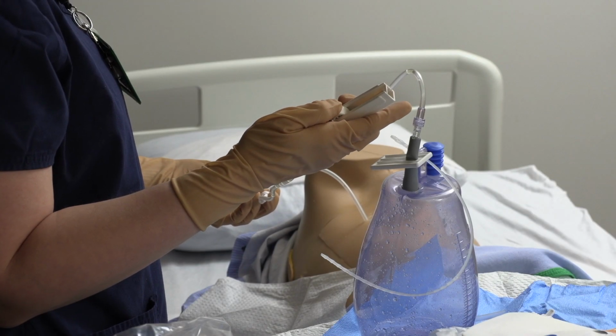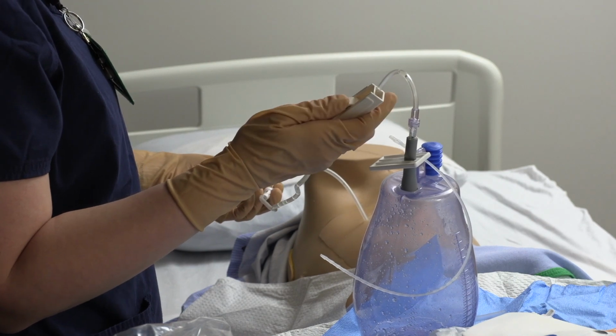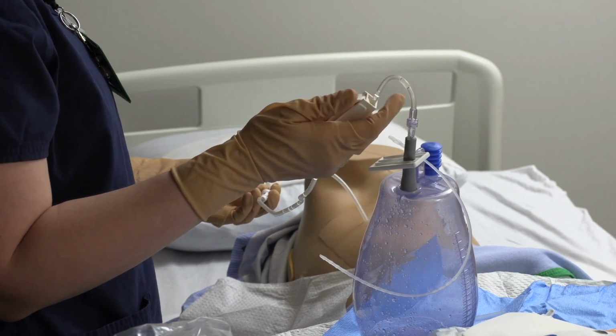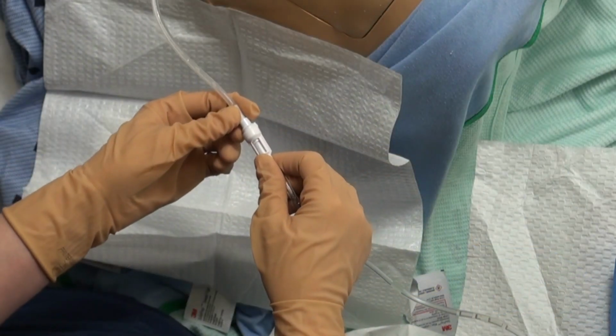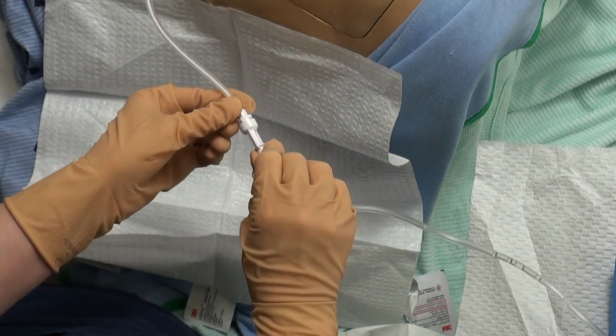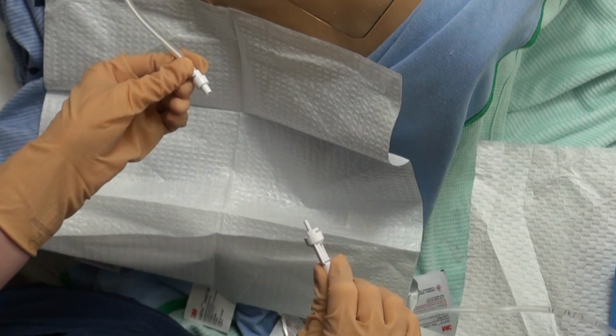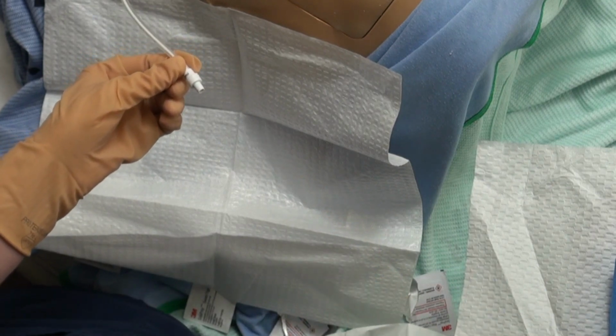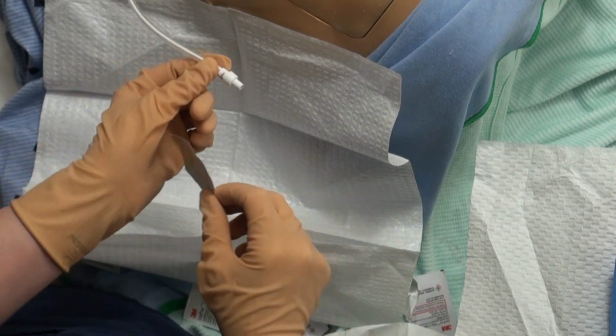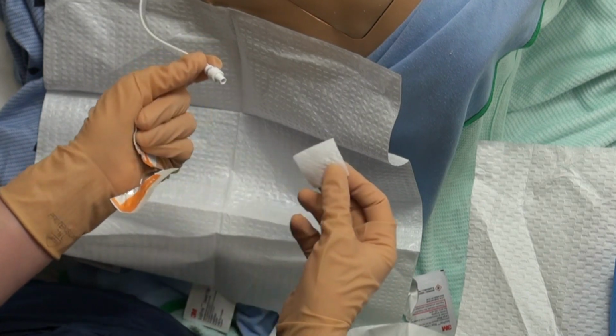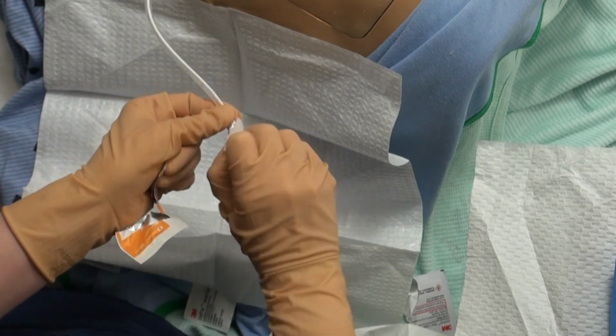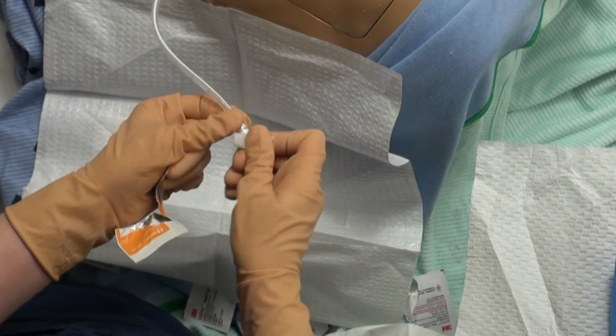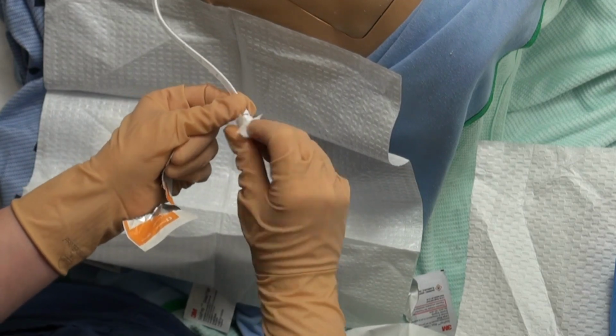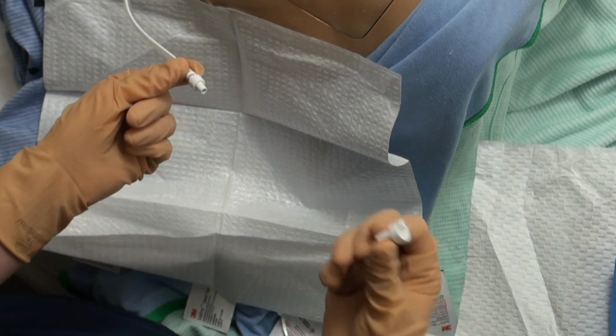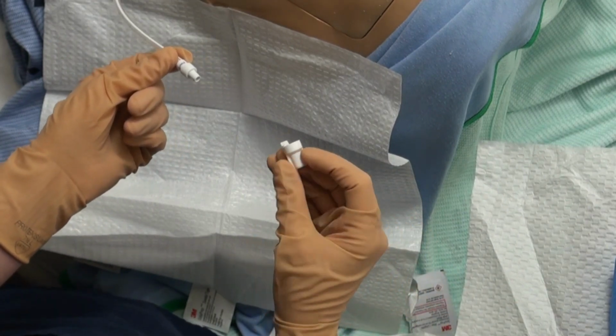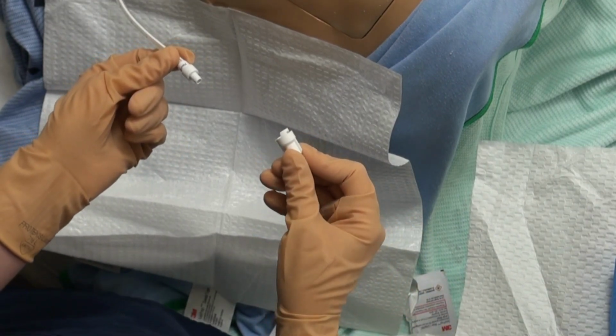When drainage is complete, close the white roller clamp completely. Unlock the drainage line access device by rotating it in the opposite direction. Remove the drainage line. Scrub the valve with the sterile alcohol swabs included in the Pleural kit for 15 seconds and let dry. Place a new sterile cap, turning clockwise until a click is felt.